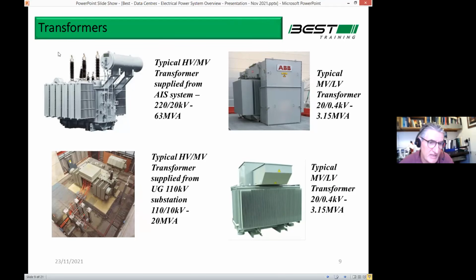Typically, that would be part of an air insulated switchgear arrangement. You can see the bushings on the transformer here. The taller ones are the higher voltage. So it comes in here at 220,000 volts. Just think of that, 1,000 times higher than the voltage in your house. And then it goes out the other side at 20 kV.